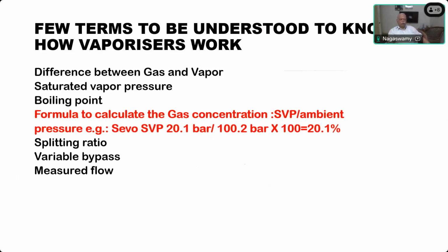Whereas in all the other vaporizers, the fresh gas flow itself causes the vaporization and picks up the vapor. Whereas here, a separate heating element and a separate holder for the liquid desflurane makes the vapor by heating that liquid, creating a vapor under pressure, which can be delivered into the passage of fresh gas flow. Of course, pictures are there later for you to understand that point easily.